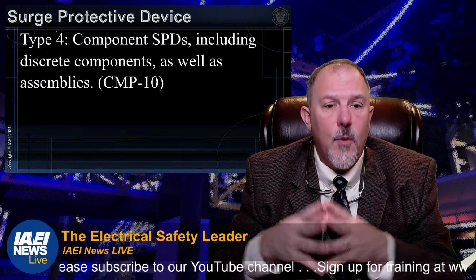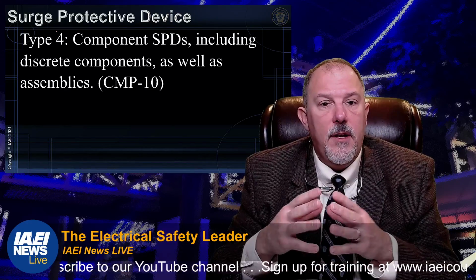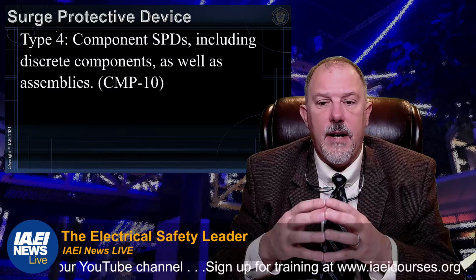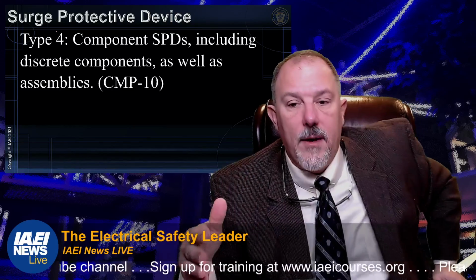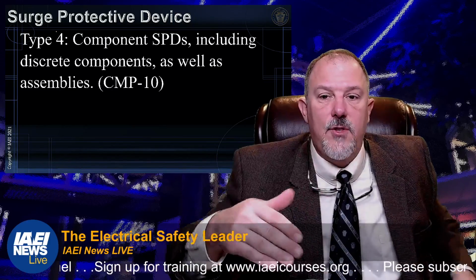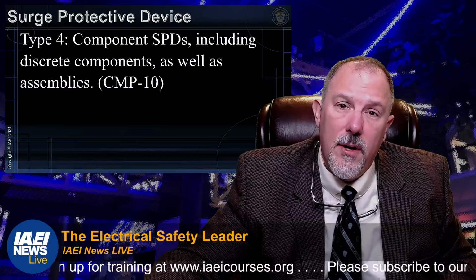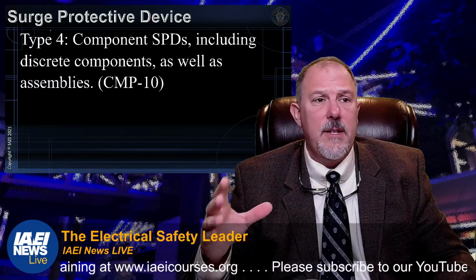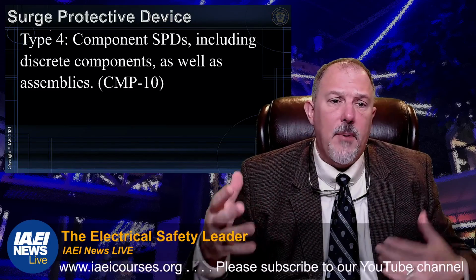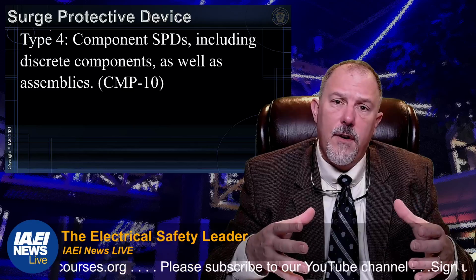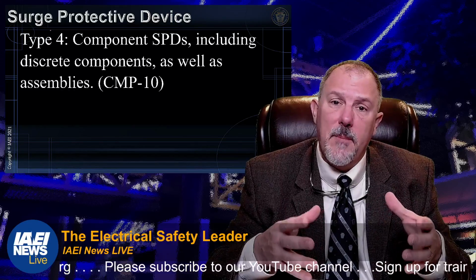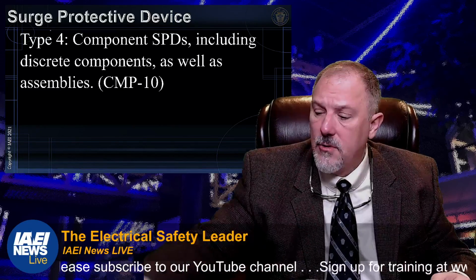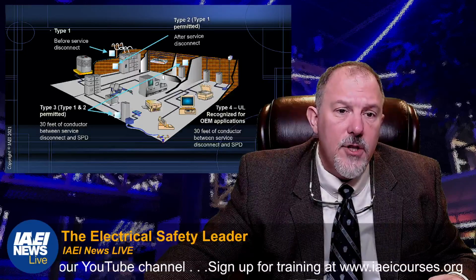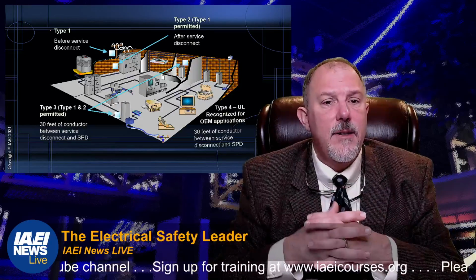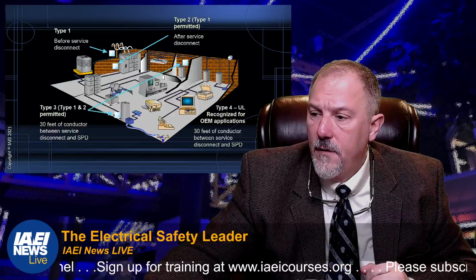And then your type 4 is a component that you might find in, say, an industrial control panel, so to speak. It's built on the board. Those are DIN rail mounted typically. They might be a part of an assembly, maybe on a motherboard, etc. Those are your type 4s. So your type 1s you'll find on the line side.